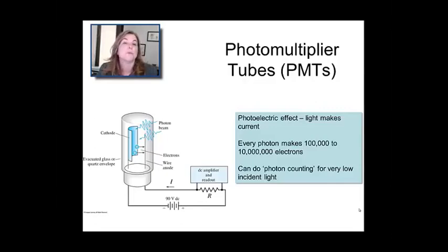If you have a system which for some reason you don't have a lot of photons to detect, then PMTs are kind of your only way to go. They're going to be most valuable when you do fluorescence spectroscopy, which I won't be talking about. For absorption spectroscopy, a little bit less valuable because usually you have a lot of photons present. Remember, you're detecting the attenuation of the light through a sample. So unless your sample is basically black, there's usually no reason to detect small numbers of photons.